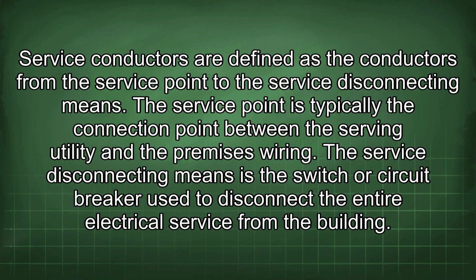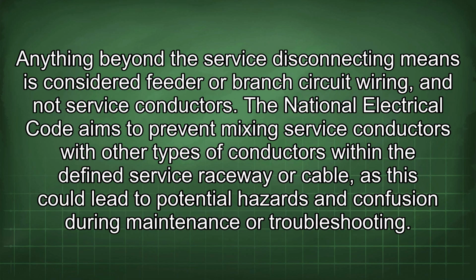Service conductors are defined as the conductors from the service point to the service disconnecting means. The service point is typically the connection point between the serving utility and the premises wiring. The service disconnecting means is the switch or circuit breaker used to disconnect the entire electrical service from the building. Anything beyond the service disconnecting means is considered feeder or branch circuit wiring and not service conductors.